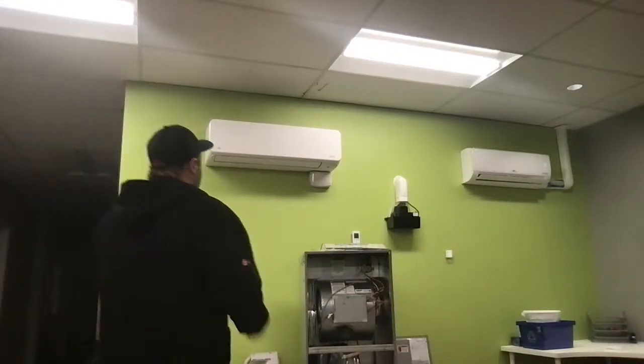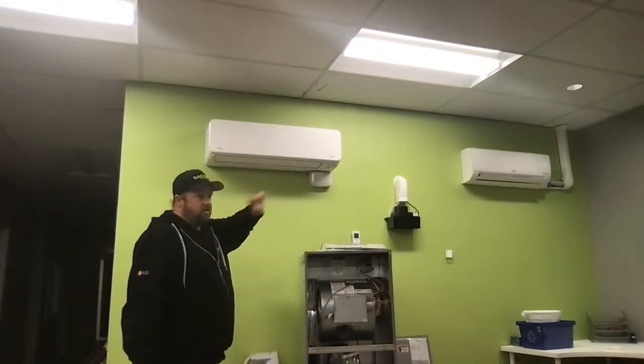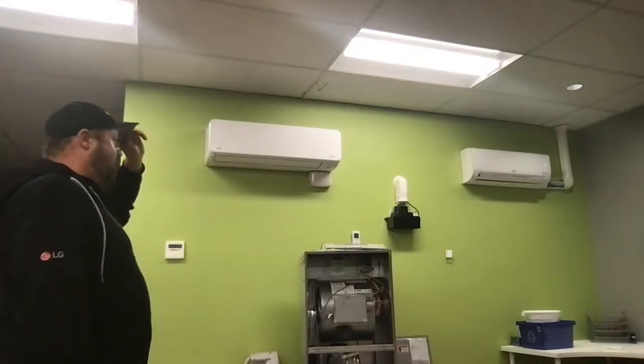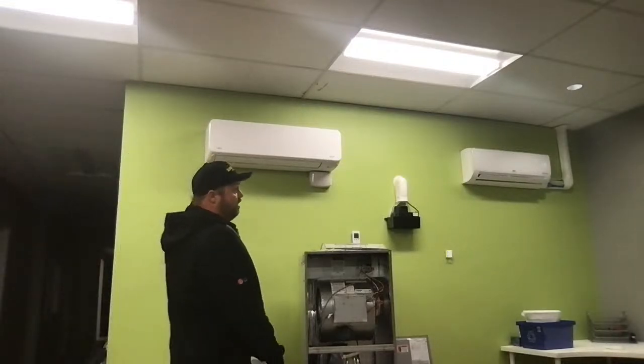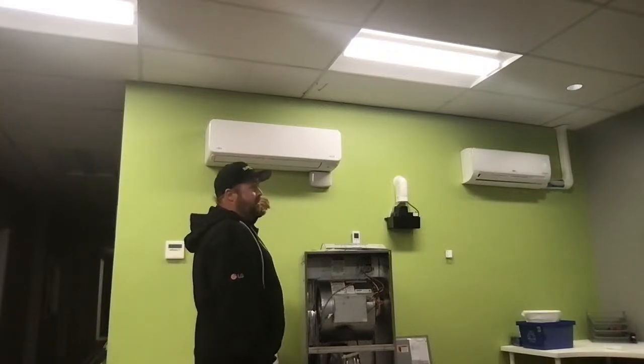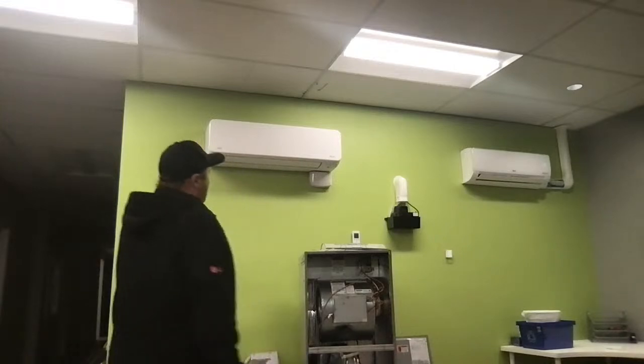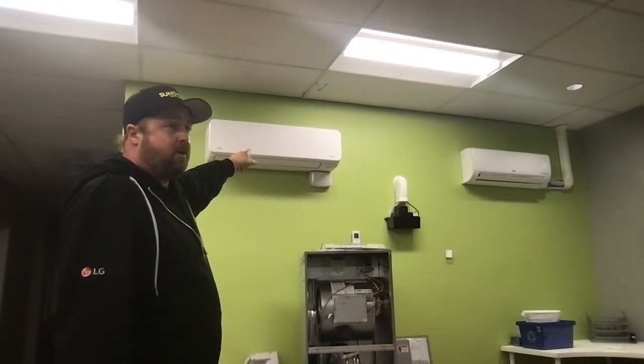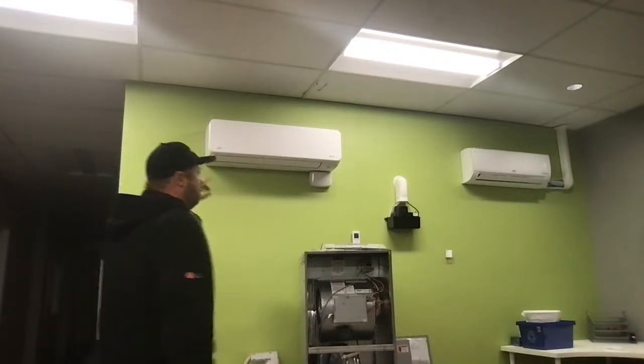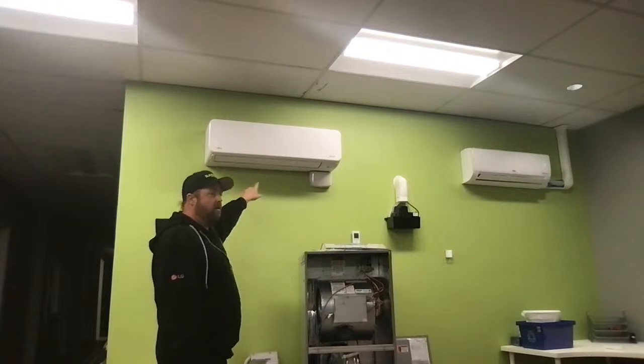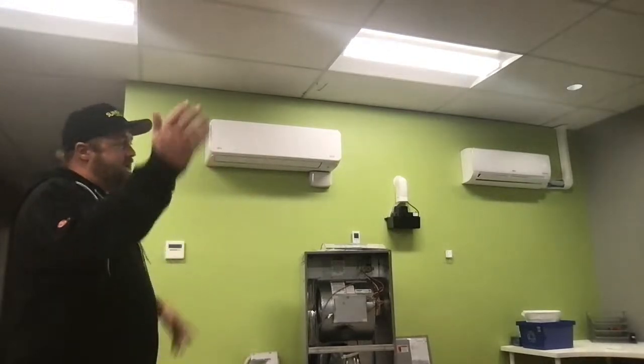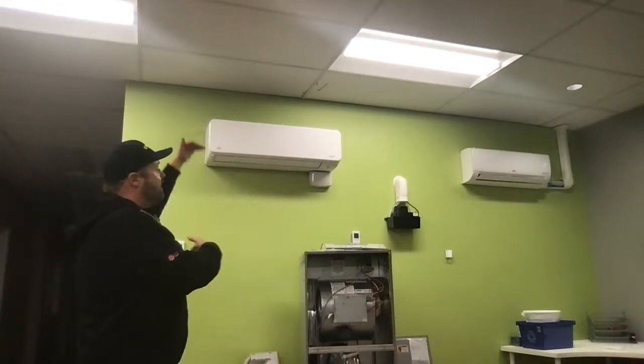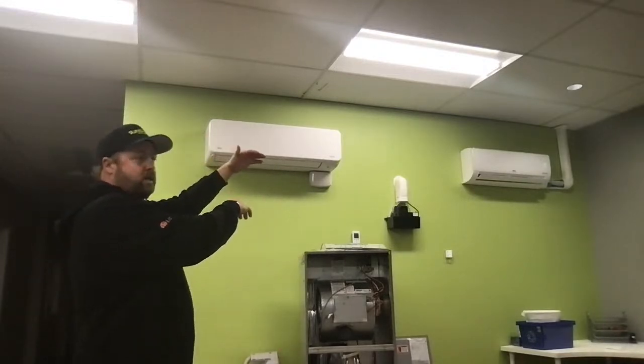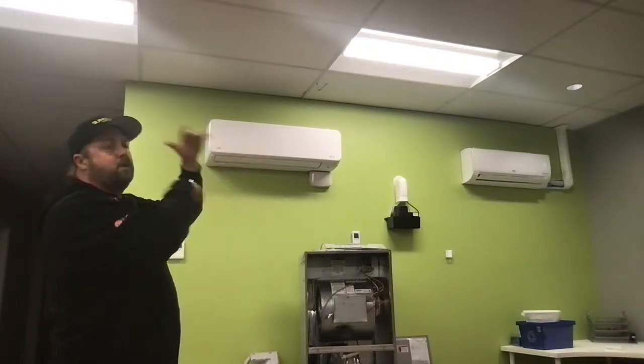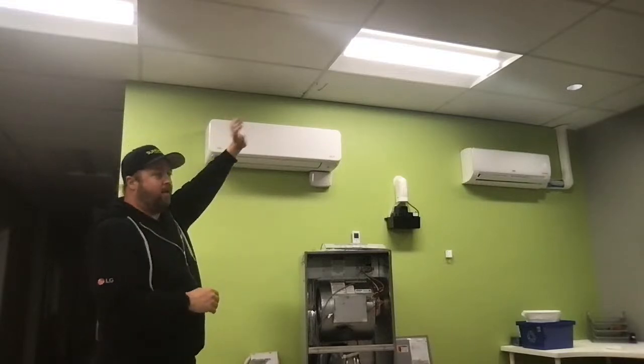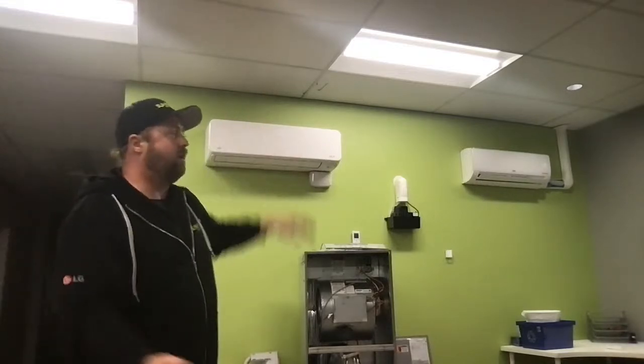One thing I'll tell you, if the unit is in the attic upstairs and it gets hot up there, someone might want to cool, even as late as December, while someone else wants to heat. It's not going to do both at once if you're on one compressor, you're either heating or cooling, not both. So you can have two zones set at 18 and 20 degrees, but they both have to be heat, or both have to be cool. You can't have one wanting 18 heat and the other wanting 20 cool. It's not going to work, the machine just shuts off.